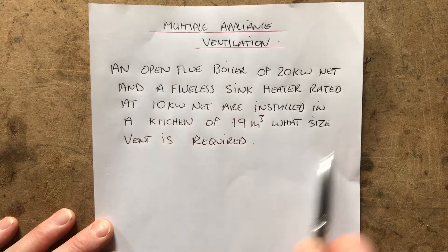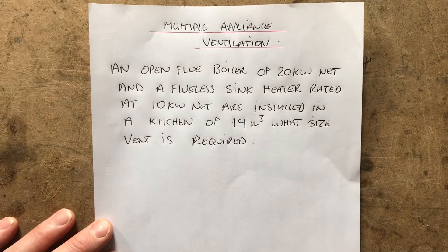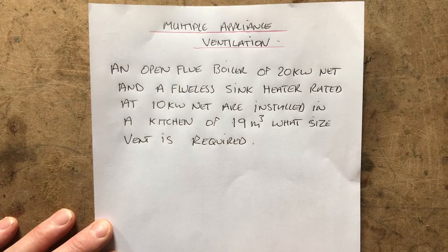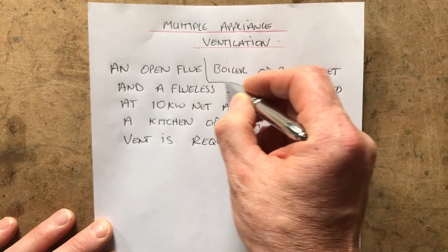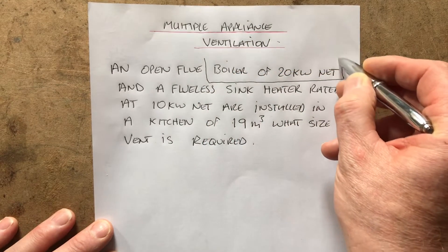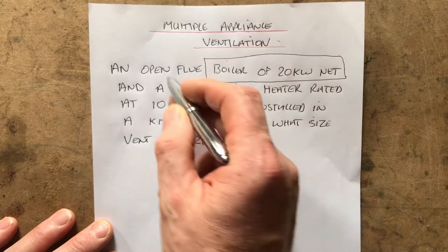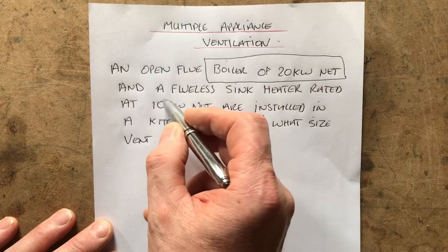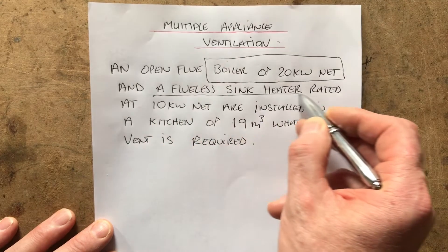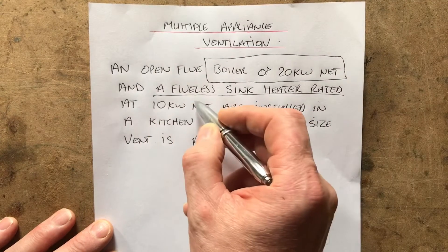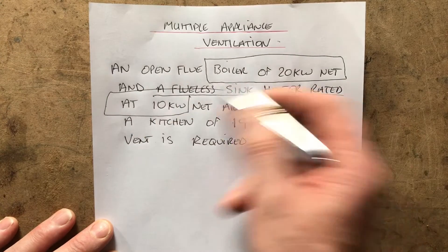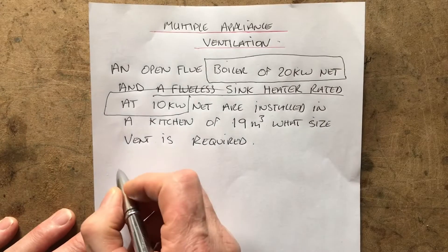Now normally when I put scenarios like this to trainees, they kind of flip out at first and think, oh no, what do I need to do? You need to break them down into their individual appliances. Our appliances are a boiler — an open-flued boiler of 20 kilowatts net — and a flueless sink heater rated at 10 kilowatts. So we'll do the boiler first.